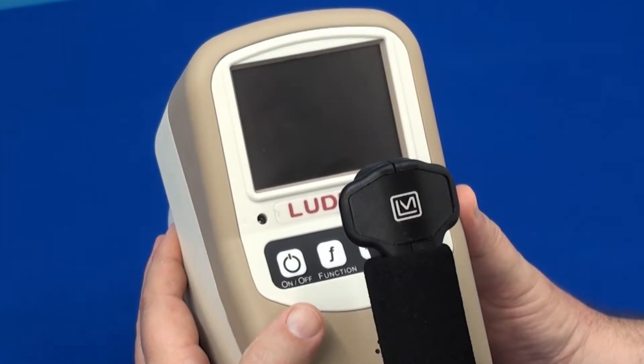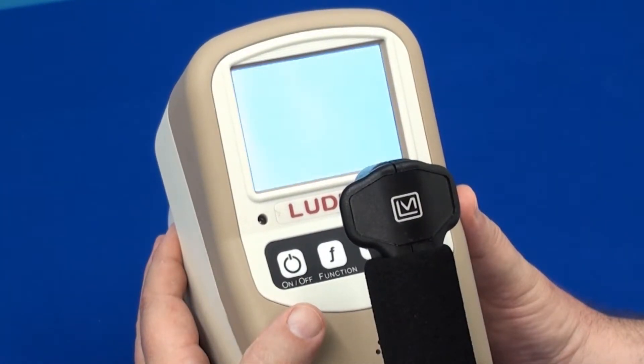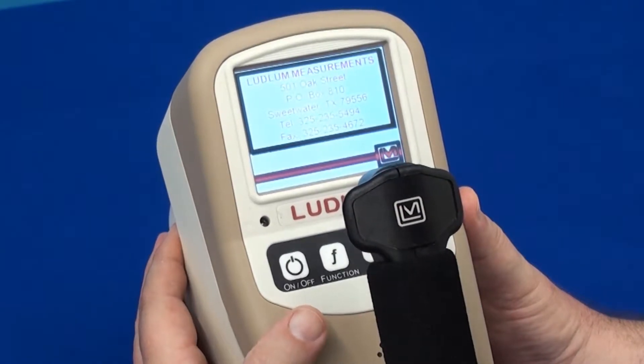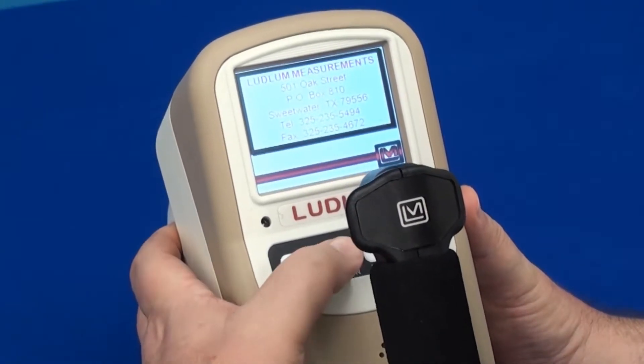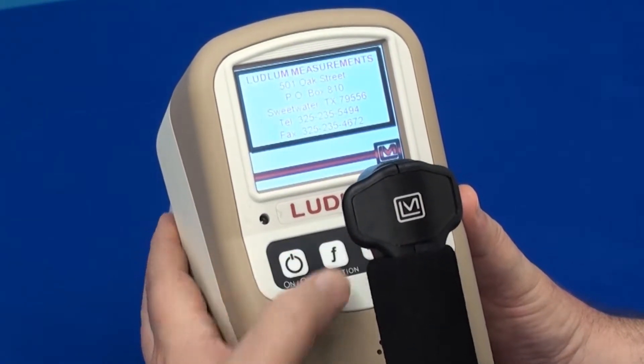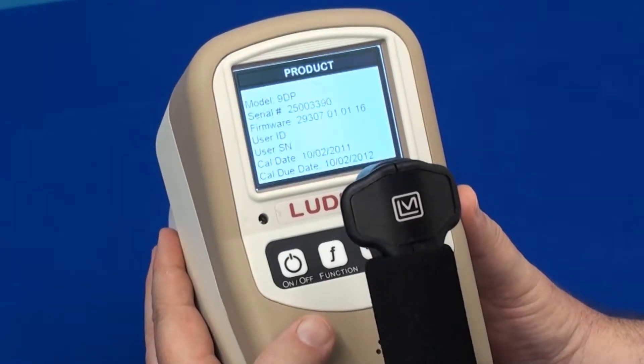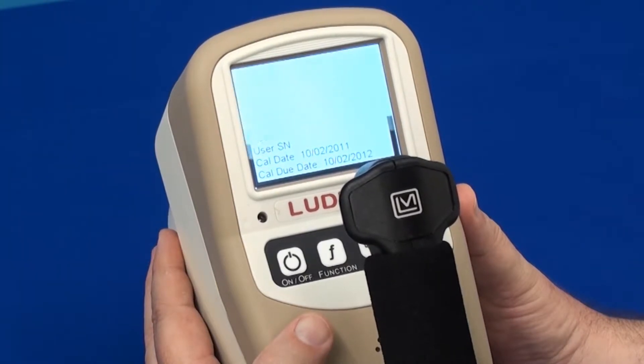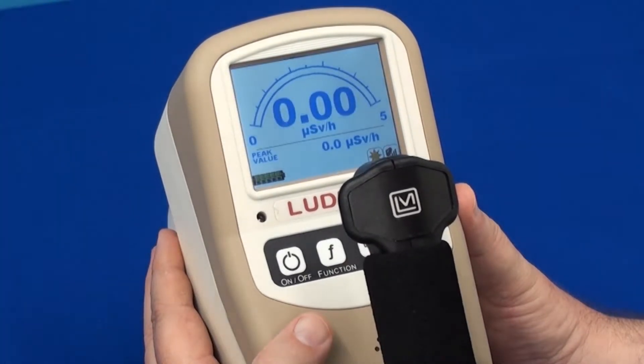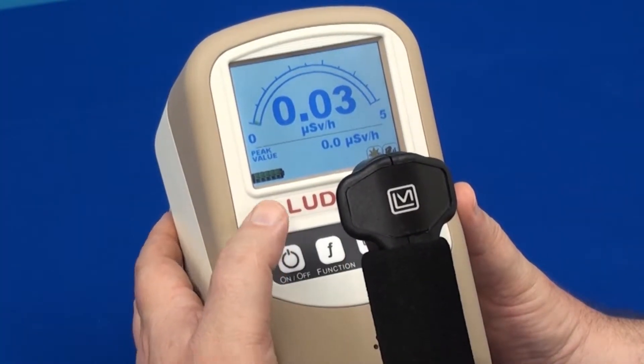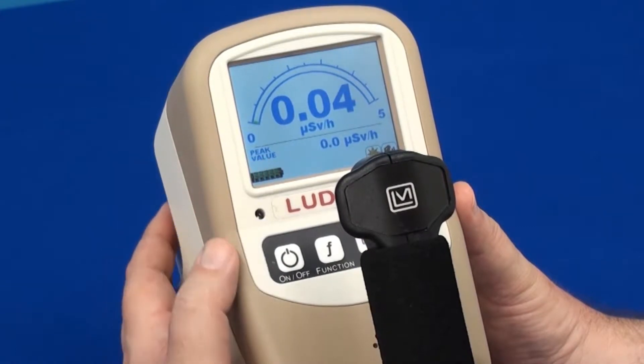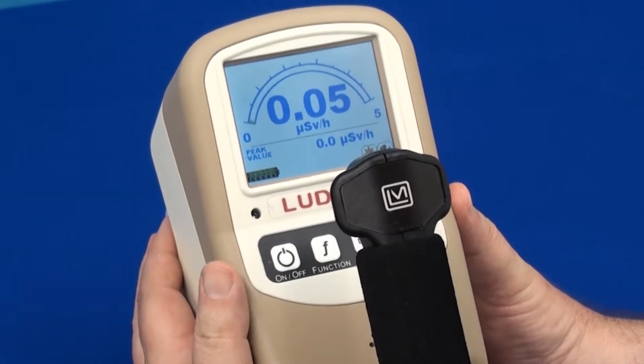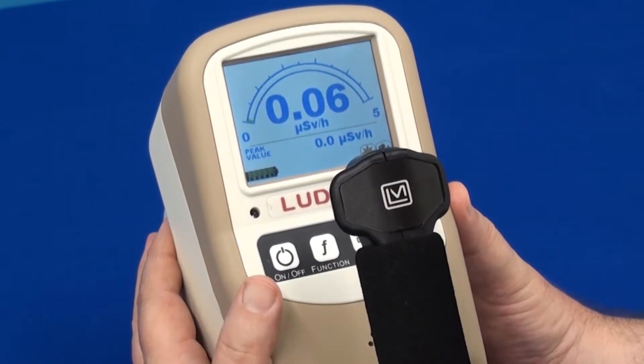In order to use the Function button, turn on the instrument by pressing the On-Off button. Once the instrument is on, press the Function button. When pressed, the instrument will scroll through its predetermined functional settings. This particular instrument has two settings: peak value and integrated dose.